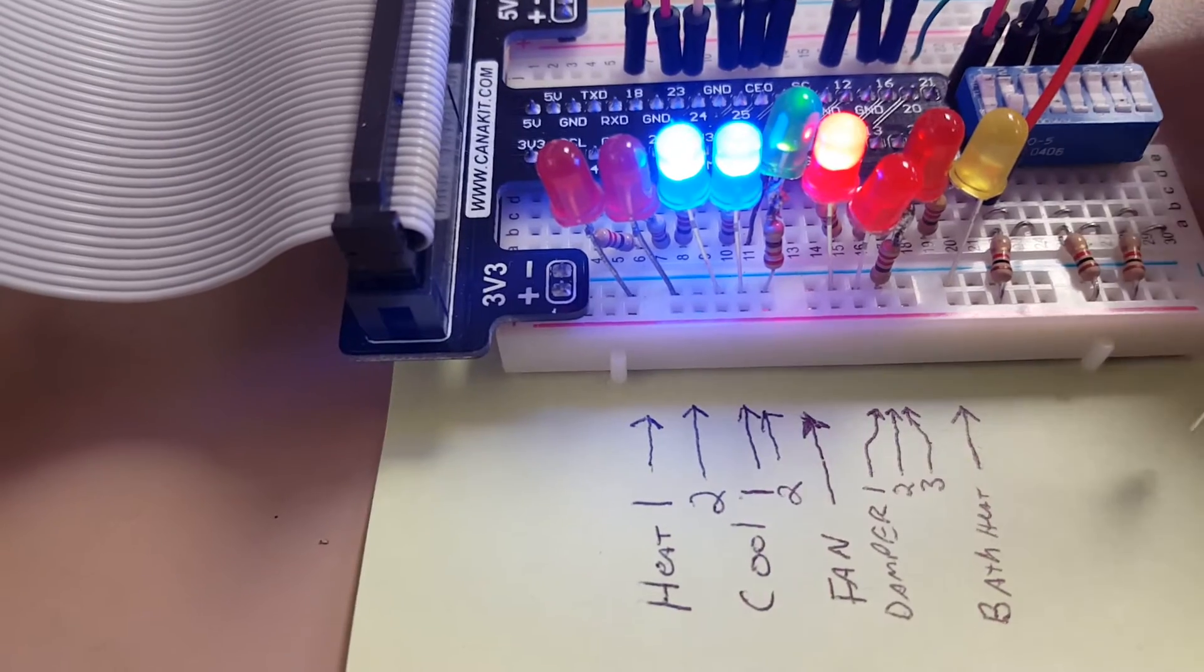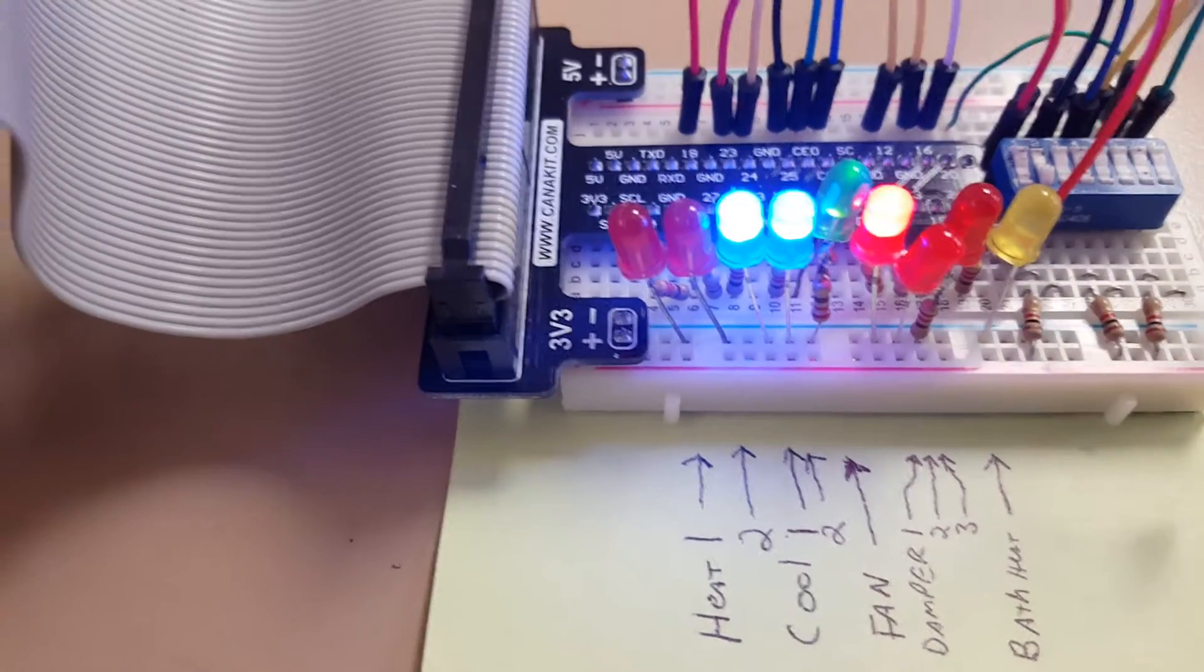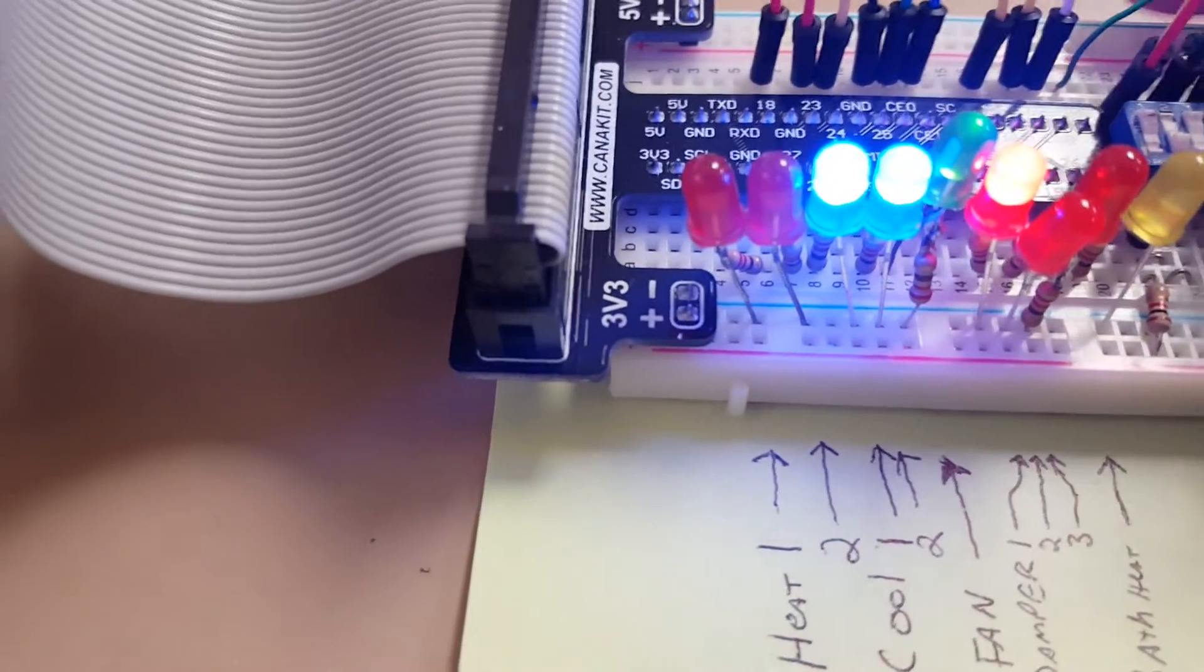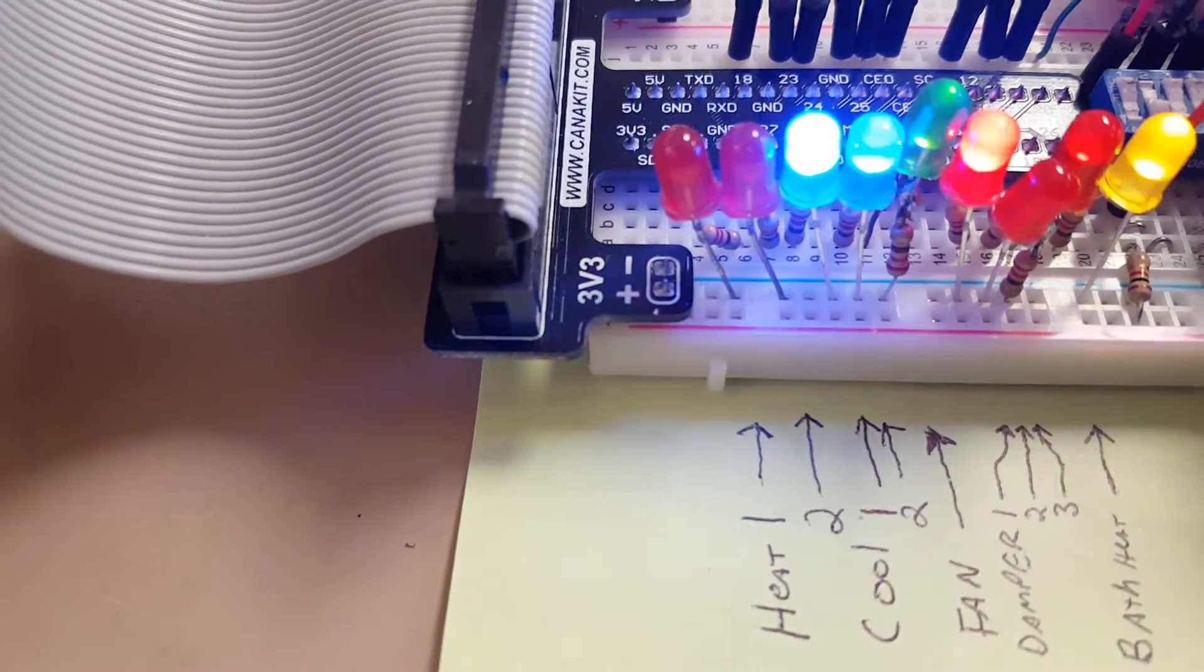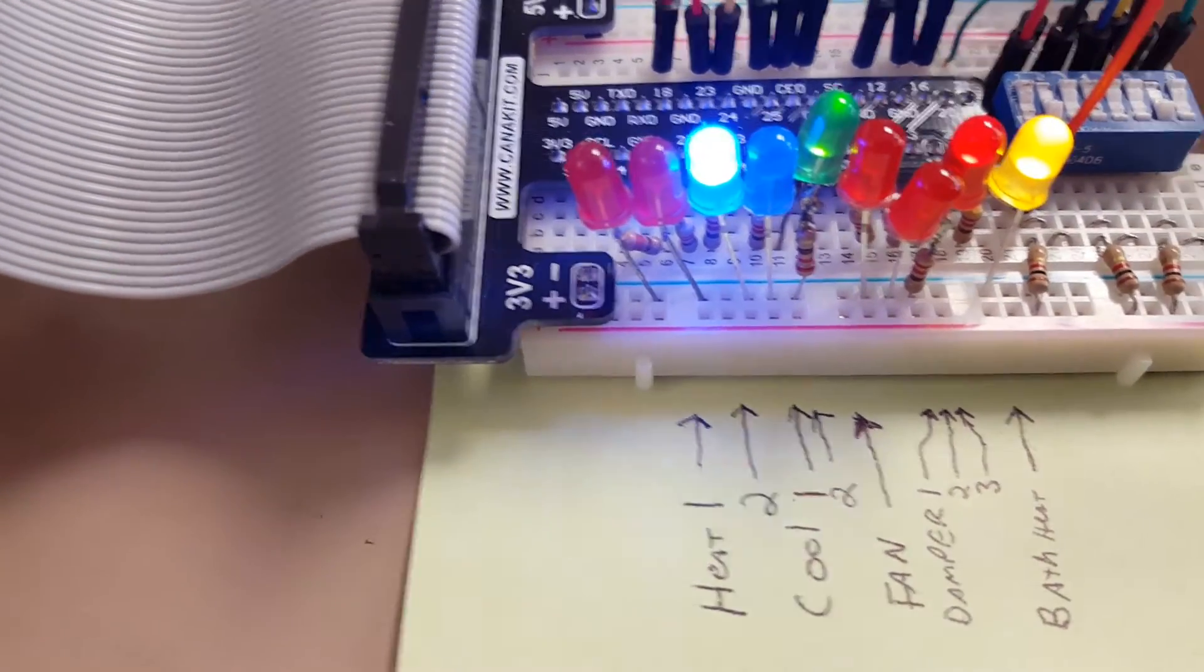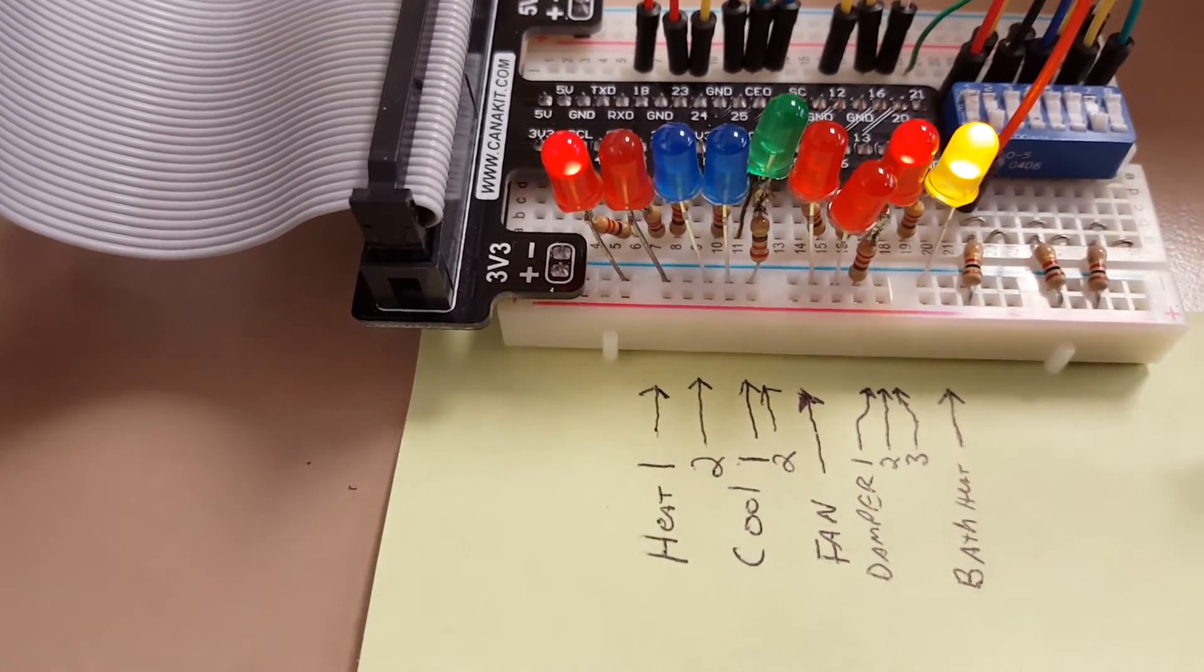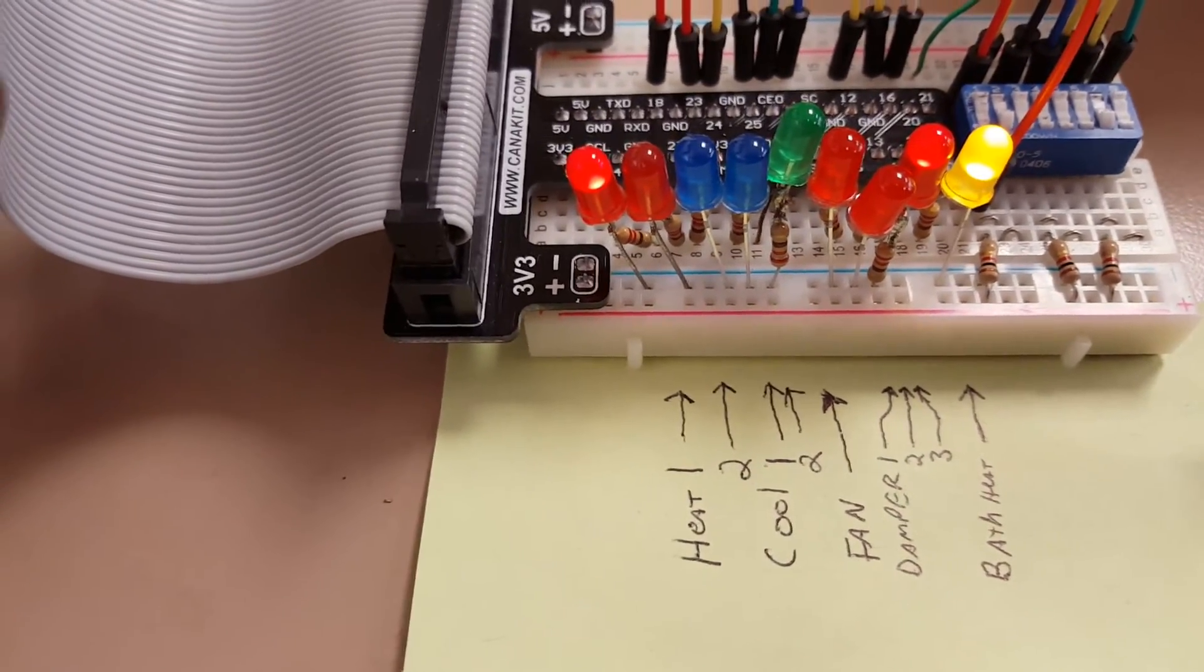One thing I built in just to make sure that heating and cooling weren't running at the same time. If the upstairs is calling for cooling and the downstairs is calling for heating, I didn't want them running at the same time, so I enabled that heating takes priority. And there you go, it's going to shut off cooling and shut off dampers to anything that isn't calling for heating.